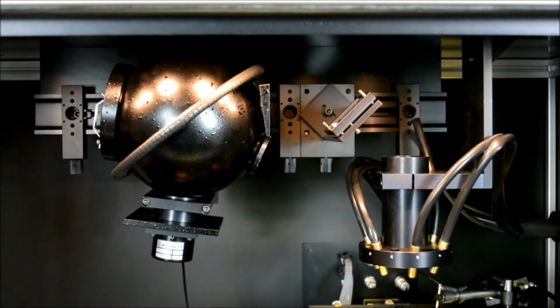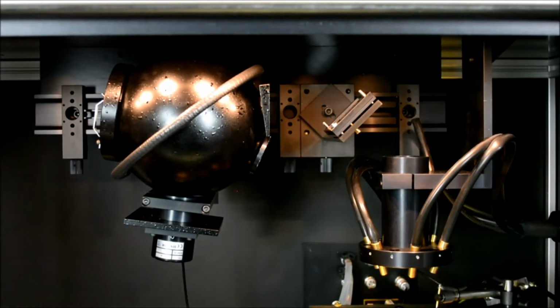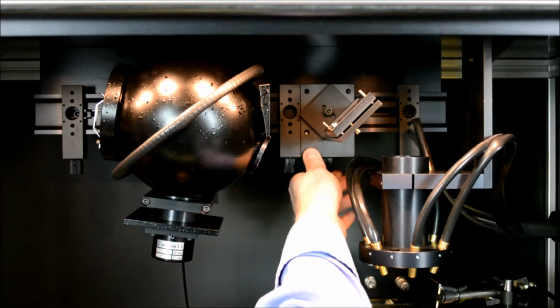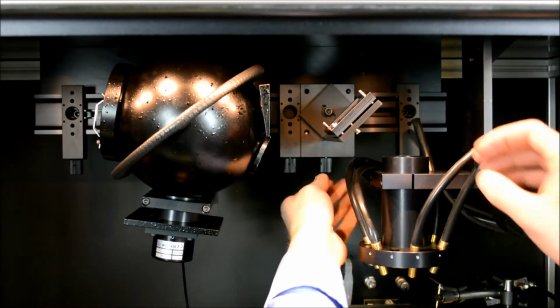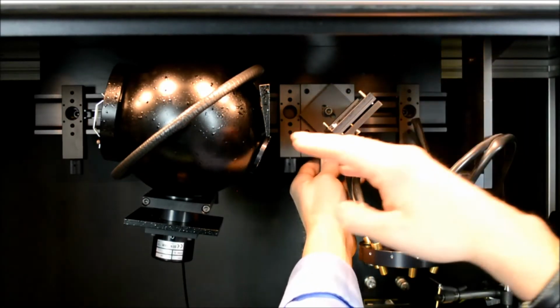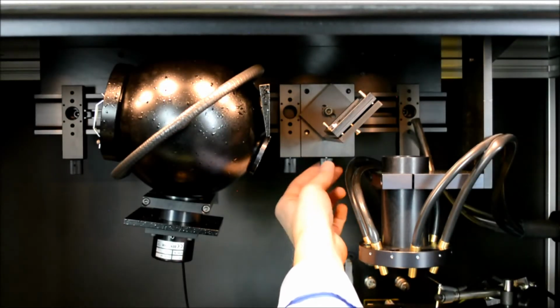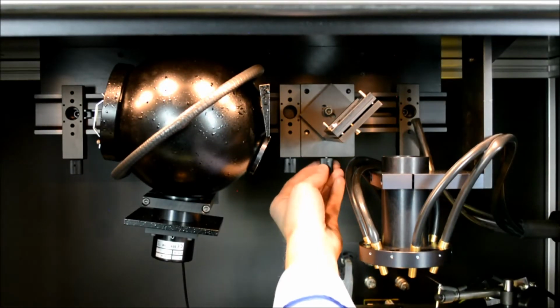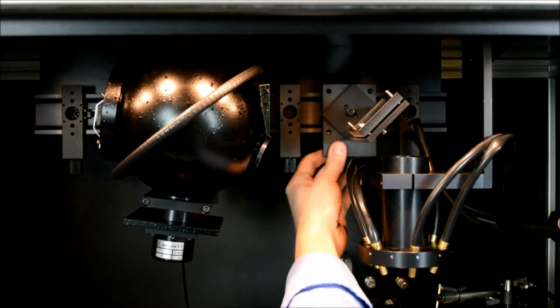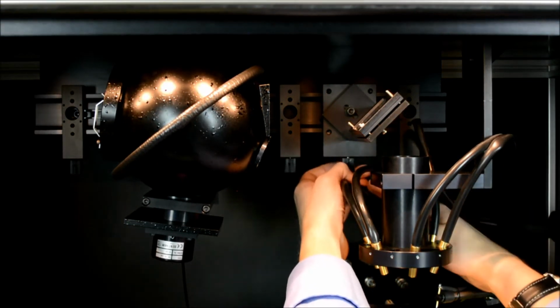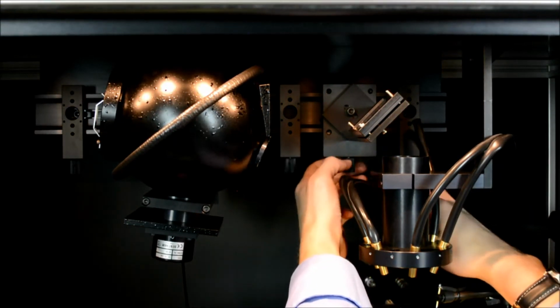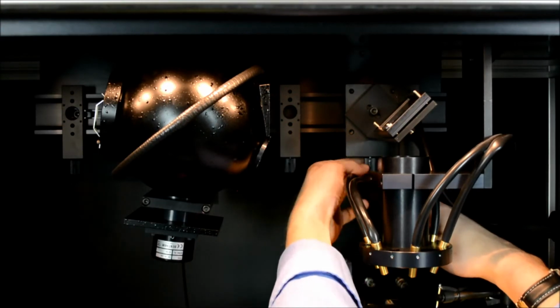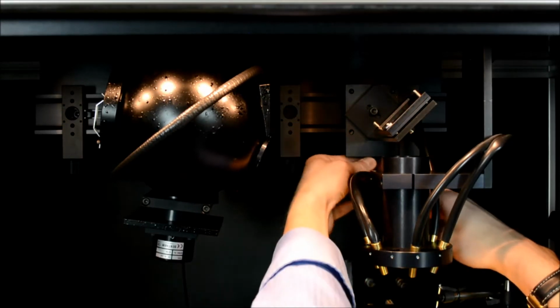We shall now turn to the measurement of spectral reflectance and spectral transmittance with the DTR6 integrating sphere. The first thing we need to do is to move the 45-degree divert mirror to the right-hand side to relay light to the DTR6. We loosen the carrier screw by a quarter of a turn to translate to the right stop, moving the fibre bundle of the bias source where it impedes the movement, and tightening the screw into position.